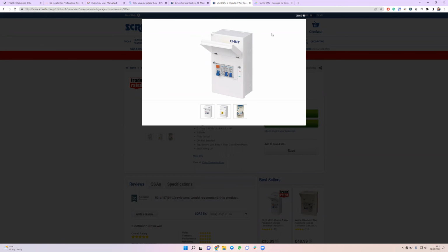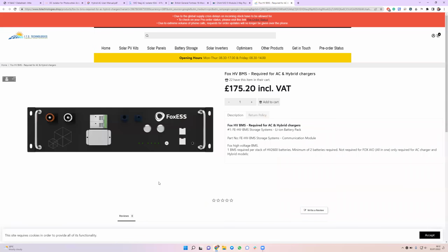Well, if you have batteries, your battery system will still be powering the inverter. So what you'll want to do is look at the very top unit that the cables connect to from your inverter to the batteries. This top unit is the brains of the battery management system, and that's what it's called, a BMS. If I annotate, you'll want to turn off the button labeled power, and you'll notice that it's recessed slightly. Push that in and release, and you'll hear a clonk, and all of these lights will go out here. Then you'll want to turn this isolator, the circuit breaker, off.